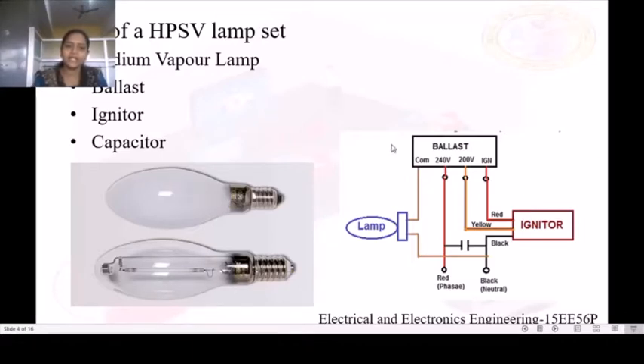Next we have an igniter. This igniter has got 3 terminals. Here the function of the igniter is to provide the high voltage pulse that is required during starting of the sodium vapor lamp. That is, it provides a high voltage pulse of about 2500 volt in order to initiate gas discharge inside the arc tube. Next, capacitor. This capacitor is used to improve the power factor of the high pressure sodium vapor lamp set.